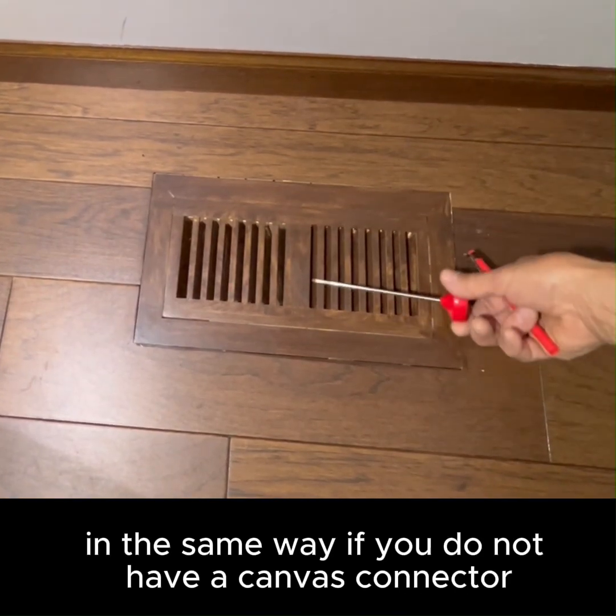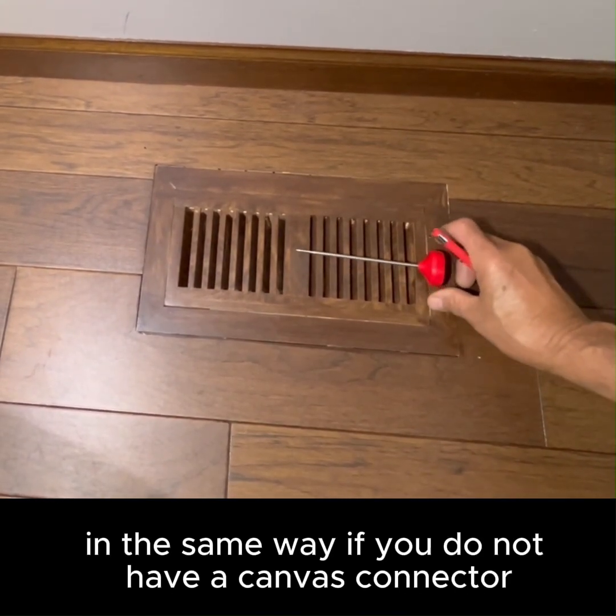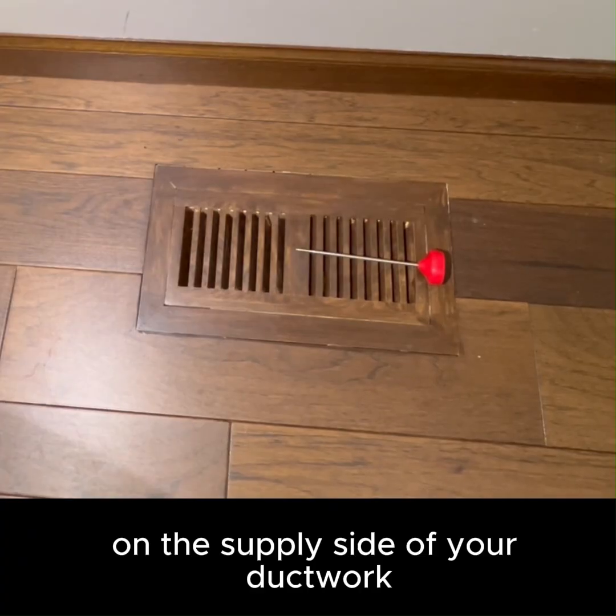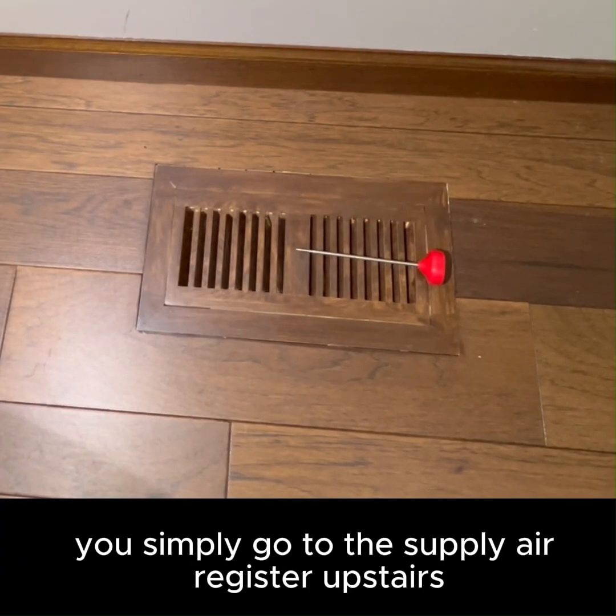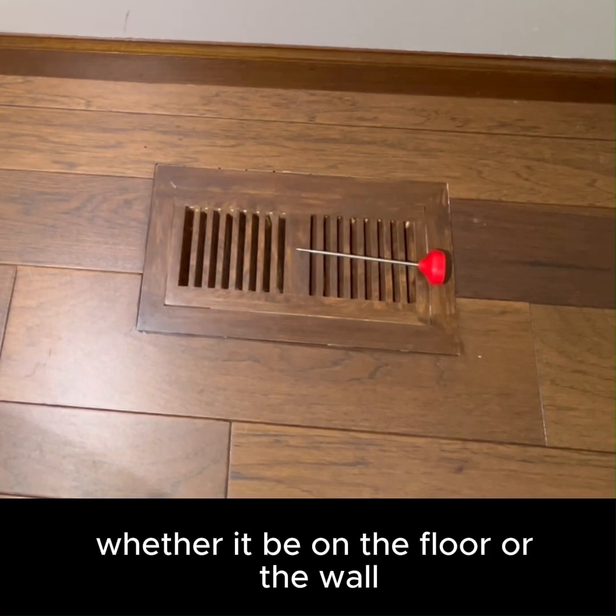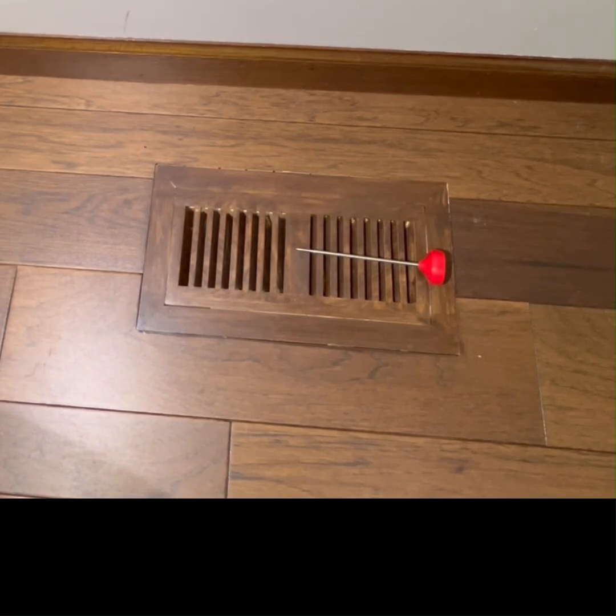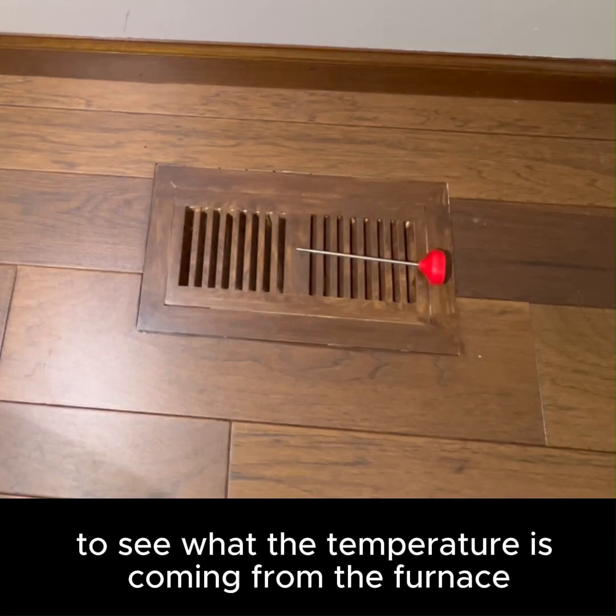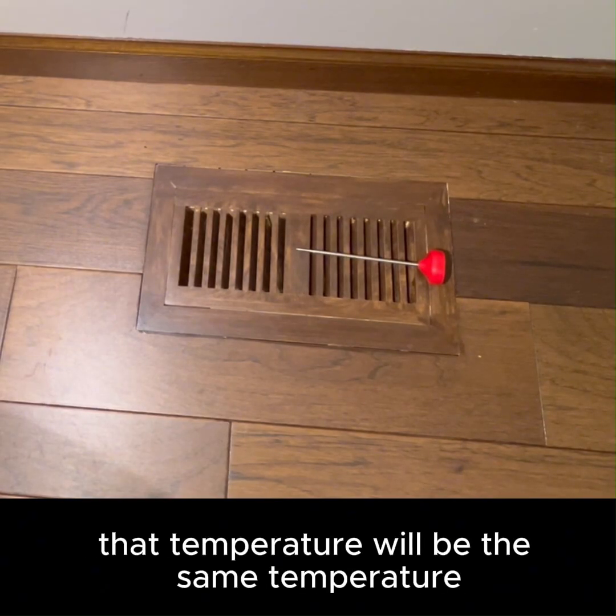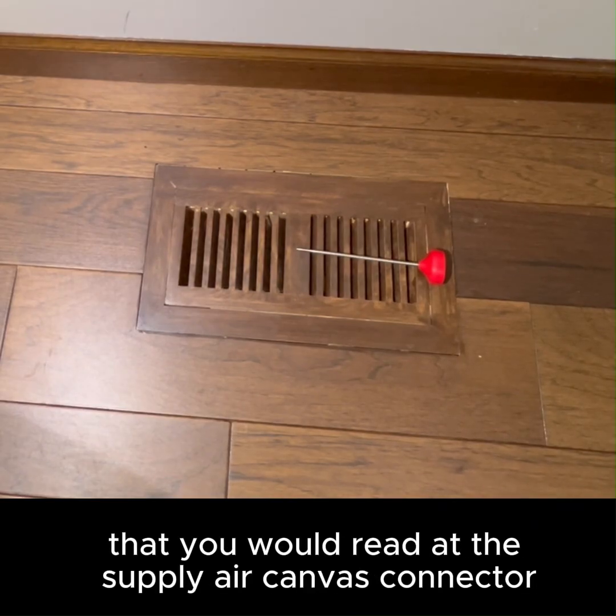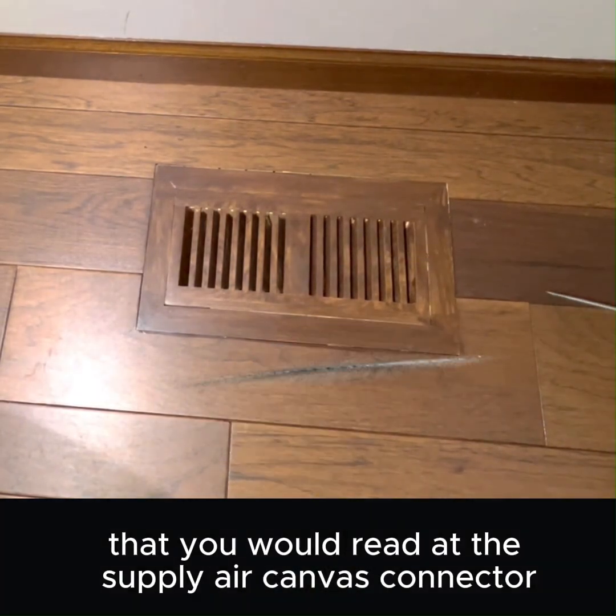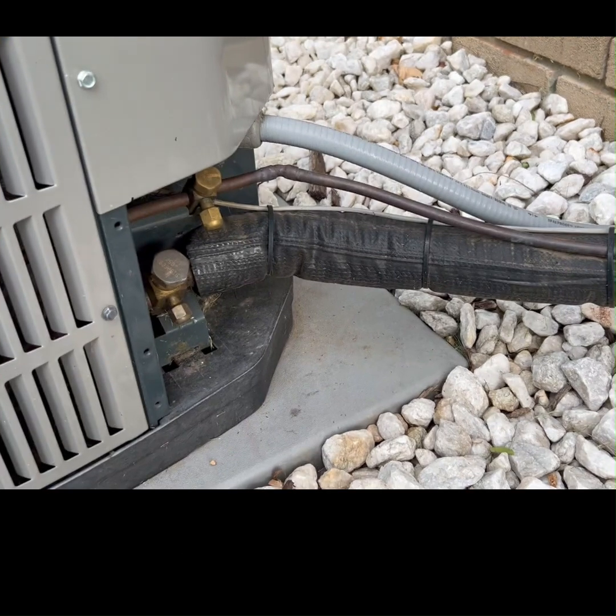In the same way, if you do not have a canvas connector on the supply side of your ductwork near the furnace, you simply go to the supply air register upstairs, whether it be on the floor or the wall. You want to check to see what the temperature is coming from the furnace. That temperature will be the same temperature that you would read at the supply air canvas connector near your furnace.